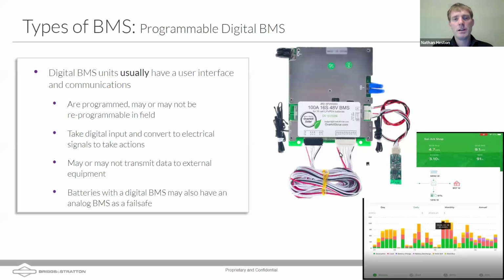This is also a programmable BMS - there's an antenna here and a Bluetooth module, which allows us to program it. A BMS like this lets us set different communication and values into the cell if we want to vary it. It allows us to take digital input and convert those electrical signals into actions using software, especially external, if we have communication like Bluetooth. It may or may not transmit data to external equipment. If you have appropriate communication like CAN bus integrated into the BMS, like our batteries do, you can communicate with external equipment like a gateway or an inverter.